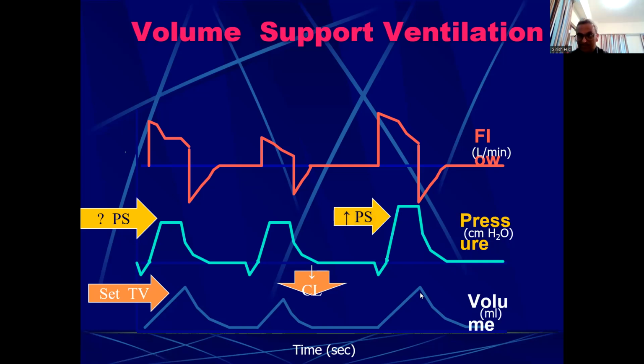In that way, this is different from pure pressure support ventilation. Volume support also uses the pressure support. But what is the big difference between pressure support and volume support ventilation? Pressure is determined by the machine. This is a closed loop, a feedback loop, whereas pressure support is not a closed loop. It is an open loop. In the sense, if there is a compliance change, you as a clinician need to increase the pressure support, correct? Whereas here, the machine does it by itself.